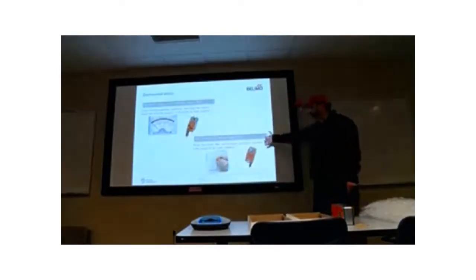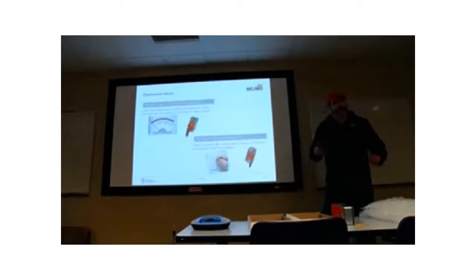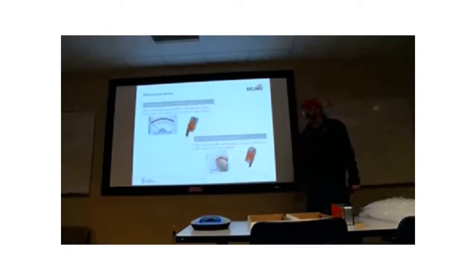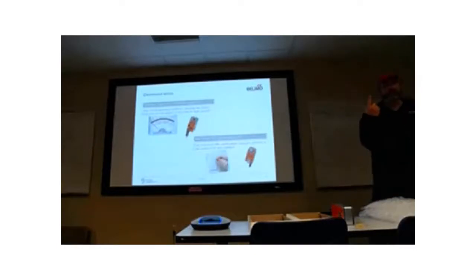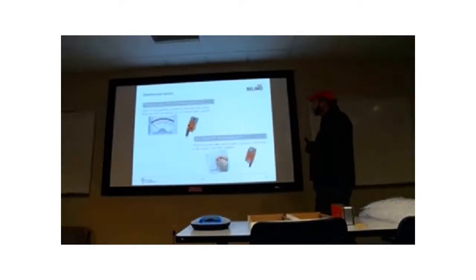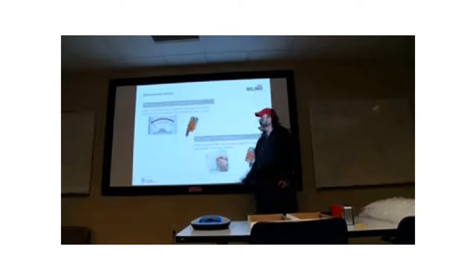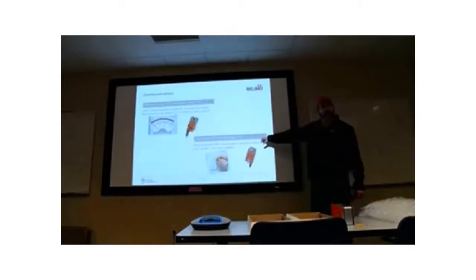The other setup is fail, right? So fail position, assuming you have a fail-safe actuator—we've got two different types of fail-safe actuators: spring return, and electronic fail-safe. Let's just talk about spring return. Spring return actuation: if you remove the power, the spring goes fail open or fail closed. Now the open and the closed refer to the damper, not to the actuator. So normal is associated with control, and fail is associated with power. Two different concepts. Okay, let's just see if we've got this thing.